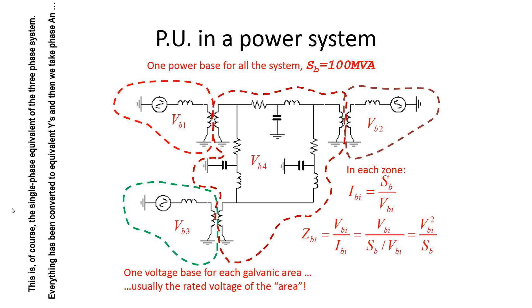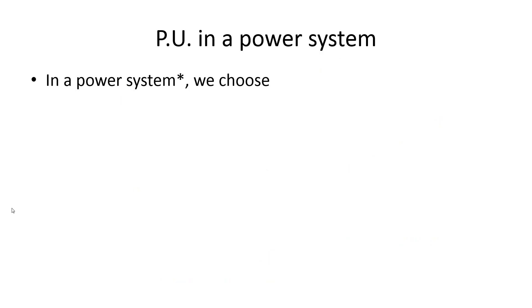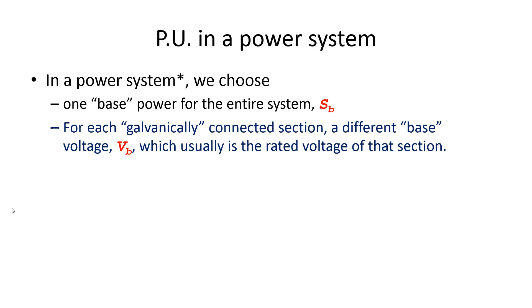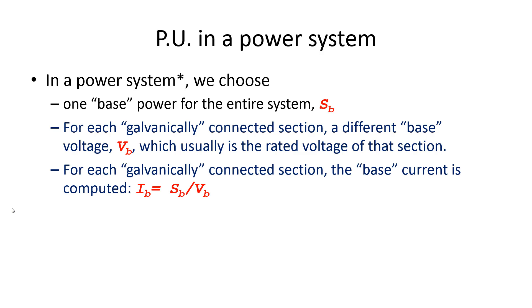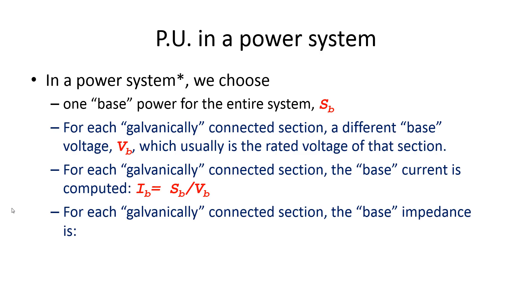A transformer has two galvanic areas; a power system has many more. To summarize: for each galvanically connected section, we choose a different base voltage — usually the rated voltage of that section — and we compute the base current and base ohms for each section.